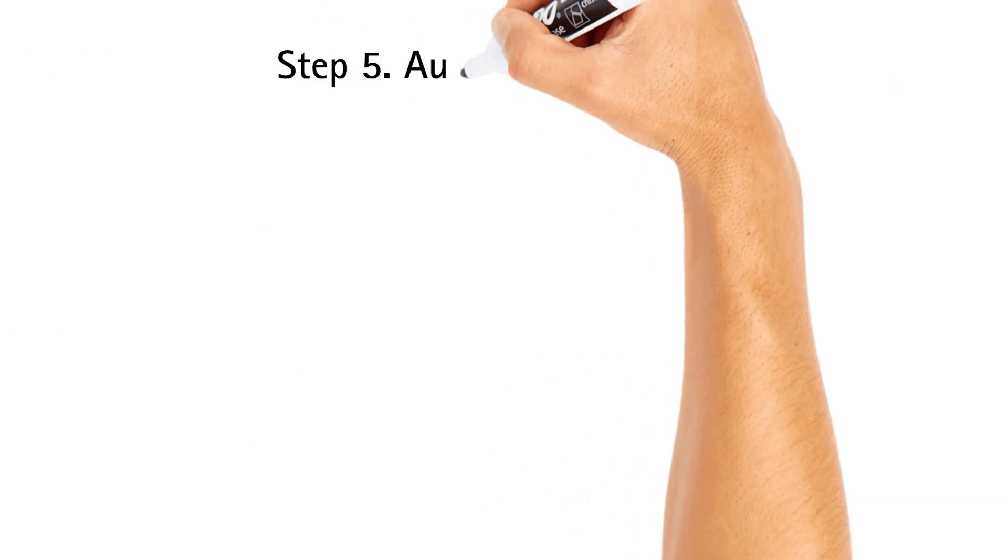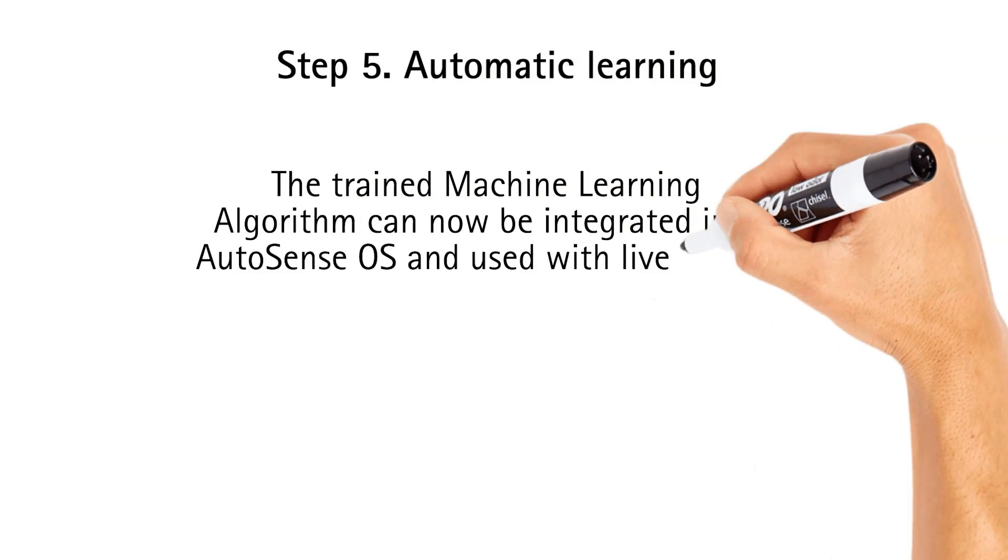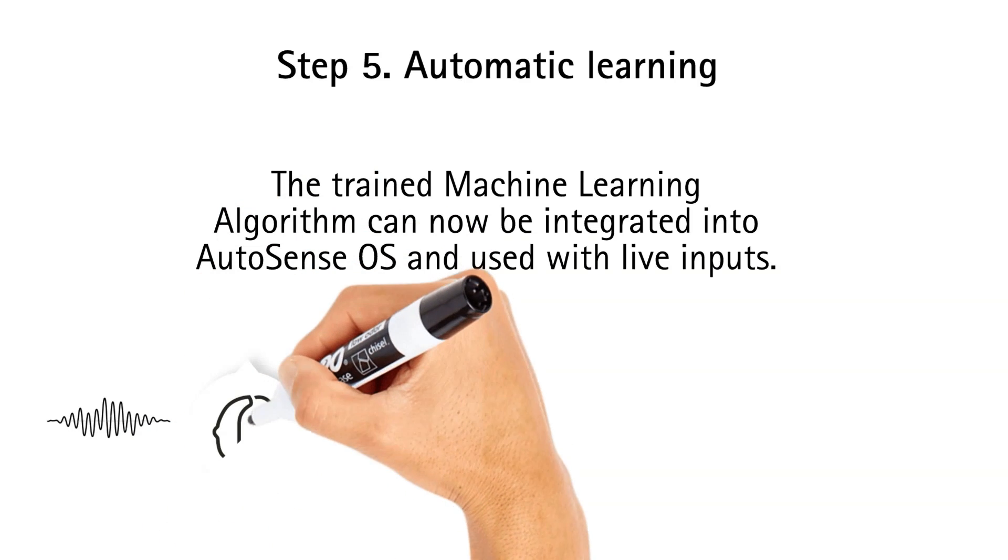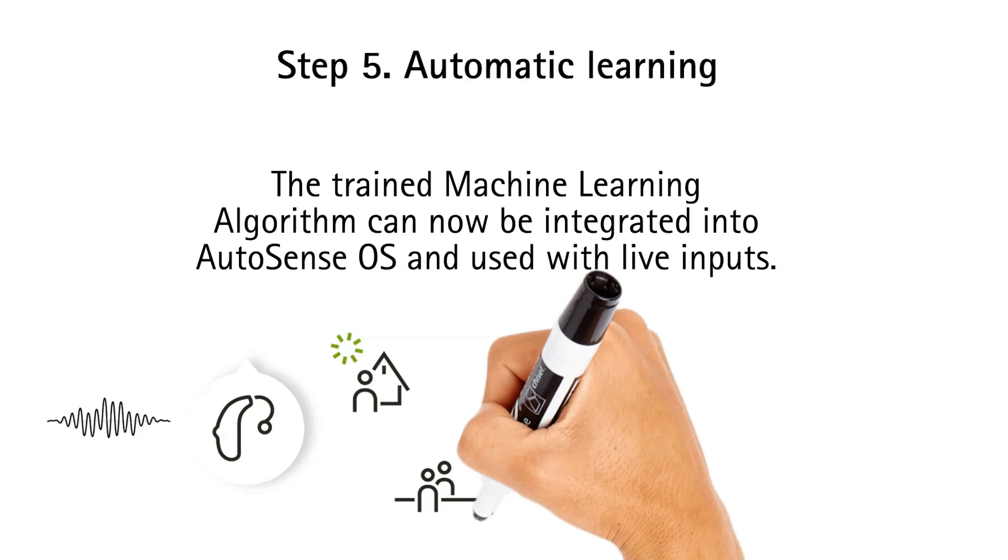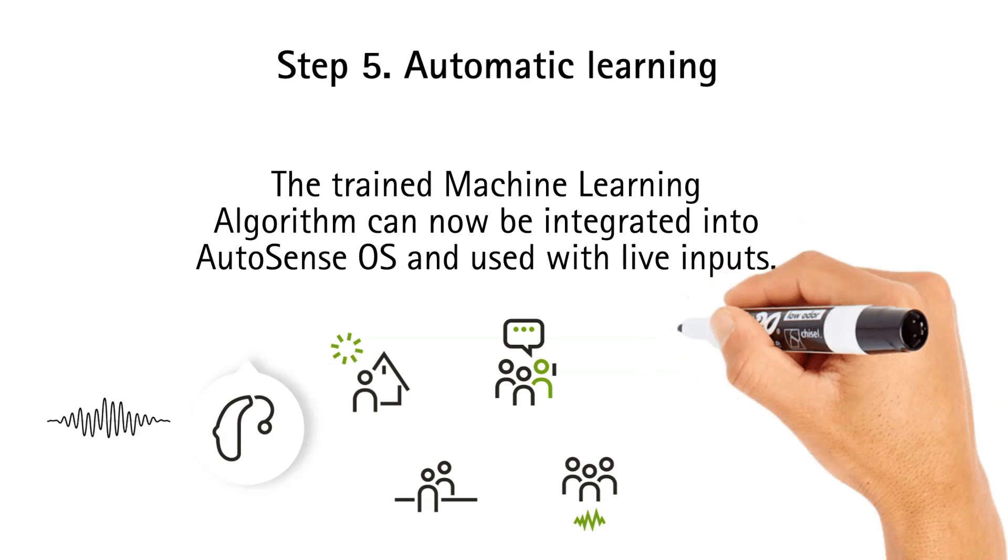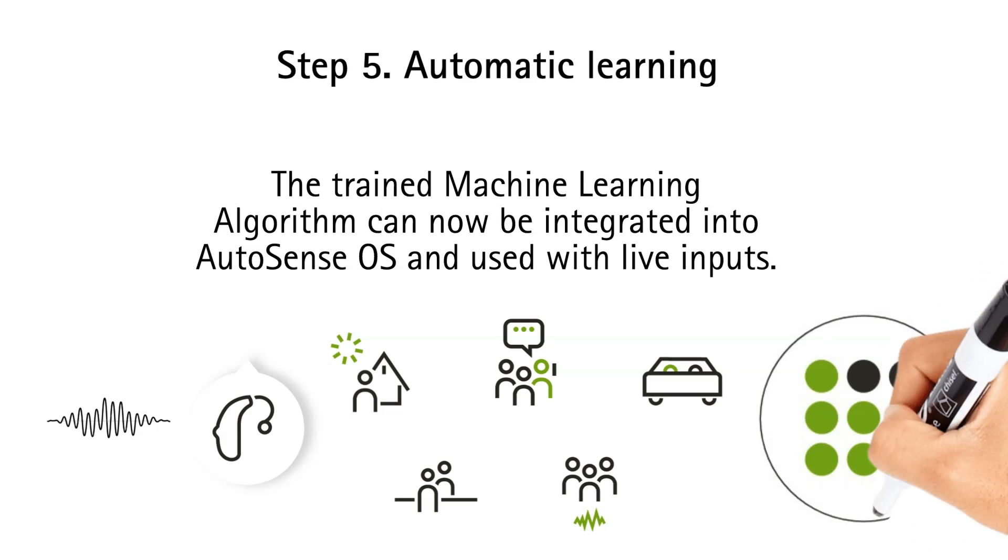Step 5 marks the phase of automatic learning. After being exposed to a vast array of sound recordings, and demonstrating consistent and precise environmental detection in controlled conditions, the machine learning algorithm is ready for integration into AutoSense OS. Now, instead of recordings, it is fed the live microphone input from a hearing aid. And it will help orchestrate choosing different possible program combinations available within AutoSense OS to ensure the hearing aid is always set to the right setting at the right time.